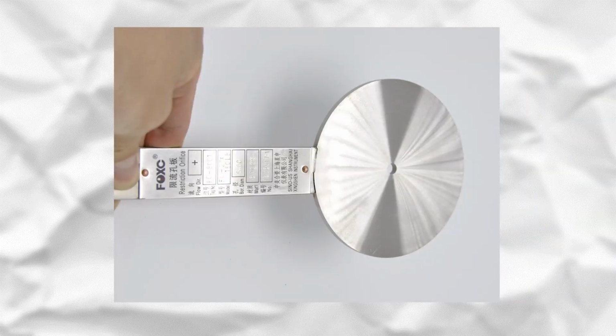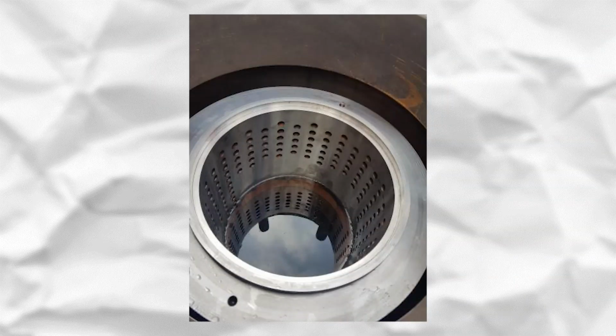Since there is a direct relationship between noise and velocity, we come to expect that in this condition the created noise is increased. As a point, the maximum permitted sound level is just 85 decibels at 1 meter distance from a valve. There are some solutions to remove cavitation. For instance, we might apply a restriction orifice after a control valve and assign a portion of delta P to it. Sometimes cavitation is inevitable, thus we have to use hardened stainless steel for valve trim material to strengthen against the cavitation effect. In addition, we can use a cage to reduce the created noise.